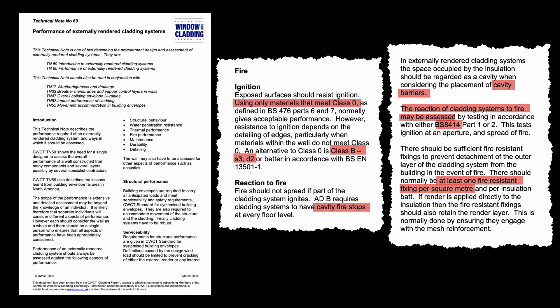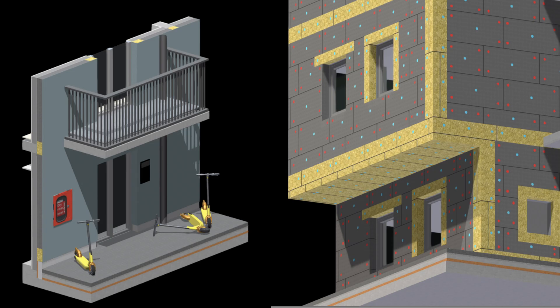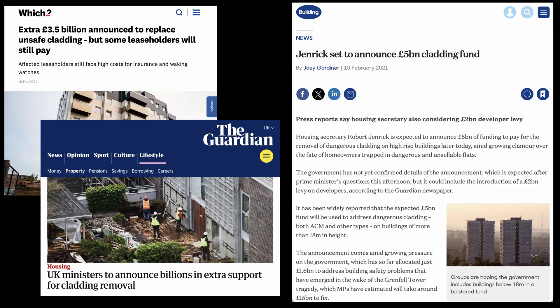This guidance, and indeed Approved Document B, makes reference to BR-135, which states that fire barriers should be considered at floor slab level starting from the second floor, or with spacing determined by the large-scale BS 8414 test — considered, but not mandated. Fire barriers around openings are mentioned as a consideration only, and again it is not clear what a 'vulnerable opening' is. CWCT Technical Note 60 on rendered cladding systems was issued in 2008 — some 17 years ago — and references class 0. To their credit, it suggests that a large-scale fire test could be useful and that at least one non-combustible fixing per square meter of system is required, and mentions cavity barriers, but makes no mention of fire barriers where there are no cavities. To make sense of all this, facade and fire engineers should be involved in the project — yet with EPS insulated render being virtually the cheapest facade system, neither is likely to be involved in small-scale low-rise buildings. Building regulations and industry guidance require updating, coordinating, and strengthening, considering how widespread and inexpensive EPS insulation is. They should consider soffits, areas vulnerable to new hazards like electric scooters, and need to be brought in line with each other.